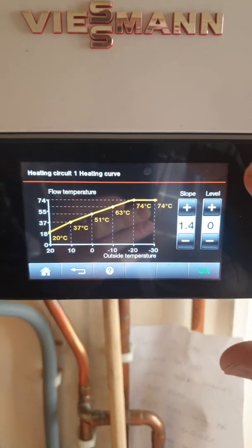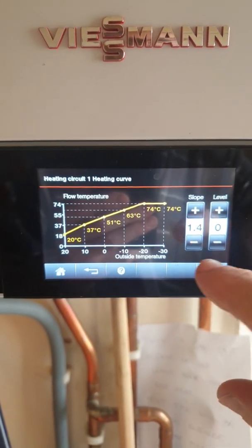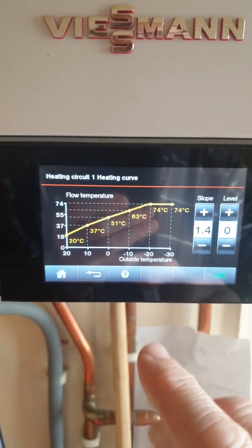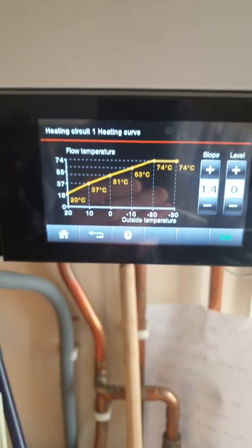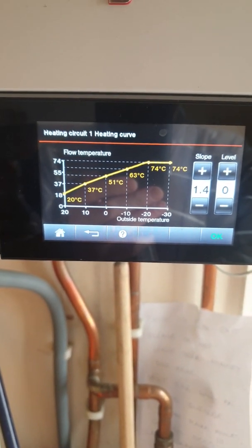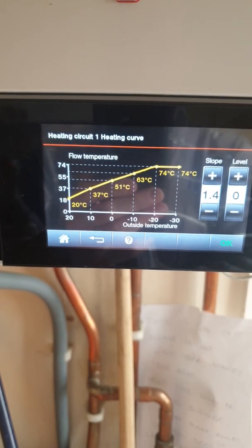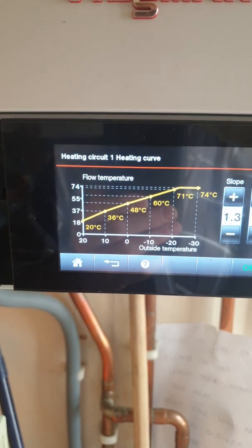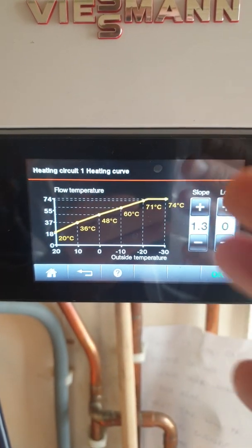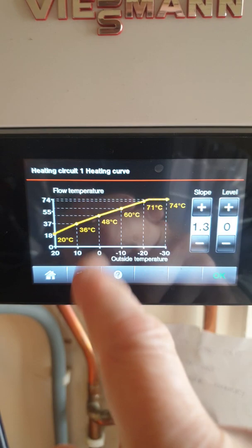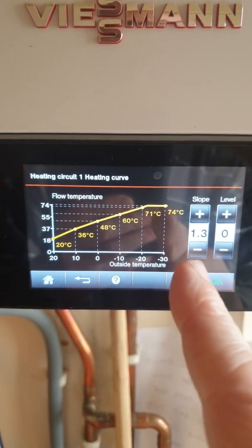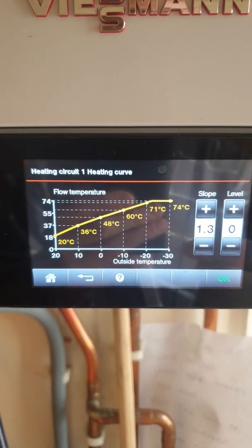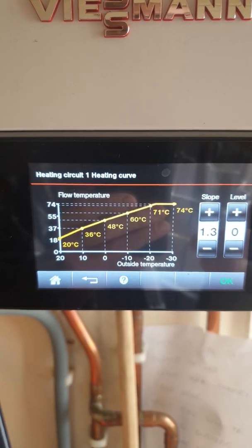So let's just explain a little bit about the weather comp here. My boiler has accidentally arrived at close to 50-30 design. You can see at zero I've got 50. The design temperature for this area is minus one, so if I had 50 degrees at minus one, that would be 50-30 design. If I go down to 1.3, you can see here that pretty much I would have 49-50 degrees at minus one, and therefore somewhere between 1.3 and 1.4 would be 50-30 design.